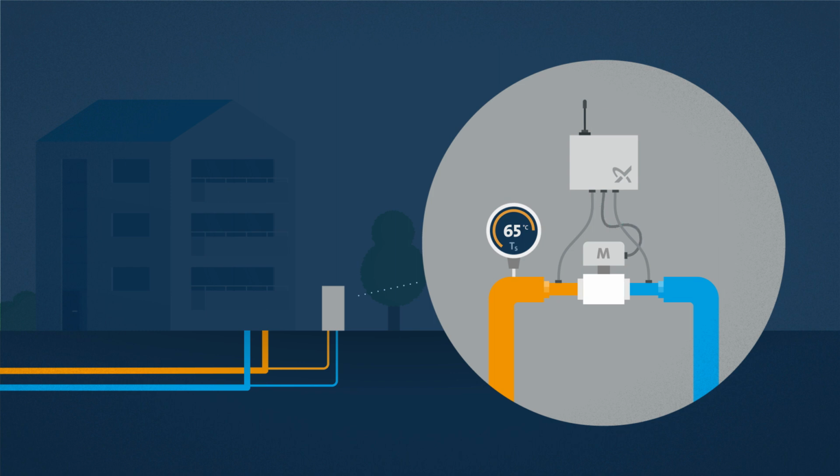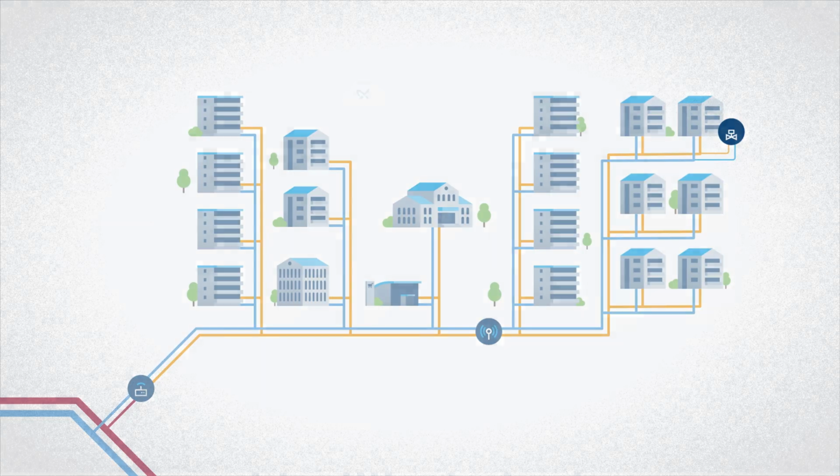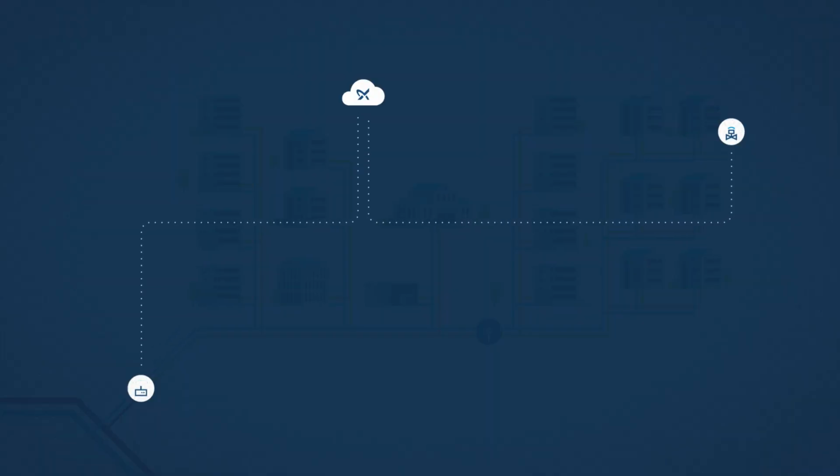During winter, where the heating demand is always high, the bypass is kept closed to avoid unnecessary heat loss and water flow. As with the iGRID pit measure point, this solution does not need to be connected to the electricity grid due to the utilization of a thermal electric generator. In the bypass, the data is returned hourly, since most of the energy is used to control the motor valve.